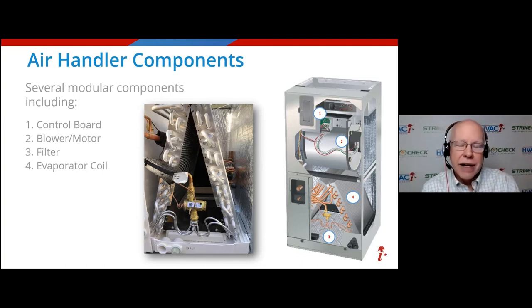So let's talk about what's going on in here, and that'll make a little bit more sense. We have the refrigerant coming in through the liquid line, through the metering device, sometimes called the expansion valve, out the bottom through those capillary tubes, looks like a little octopus there. And it is a cold liquid refrigerant, all right? Remember, outside it was a hot gas refrigerant. Inside it's a cold liquid refrigerant, completely different, and it's going through the A coil, all right? The blower's going to be bringing warm, moist air to it. And when you force that warm, moist air through the coil, guess what happens? The second law of thermodynamics for the second time. The heat leaves the air and goes into the refrigerant. And by the time the refrigerant leaves the A coil, it's a warm vapor being taken out through the suction line. So now you've got the complete circuit going there.